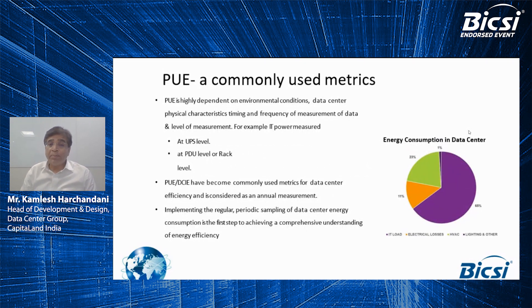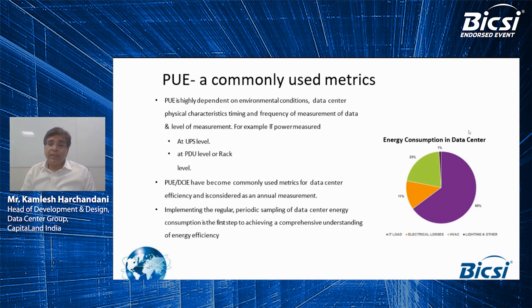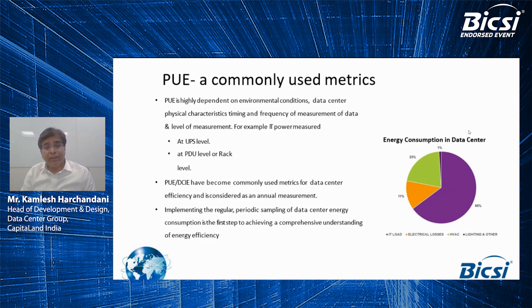Let's talk about PUE — Power Usage Effectiveness. The ratio of PUE is the total facility power for the data center divided by IT load. PUE was introduced by the Green Grid in 2007. We can check the total facility power requirement; however, to measure the IT load, there are three levels: one at a UPS level, second at a PDU level, and third at a rack level. This is how you calculate your PUE for your data center facility.